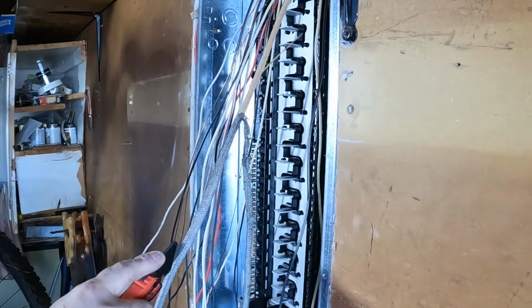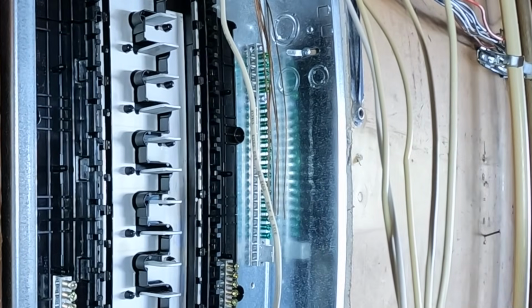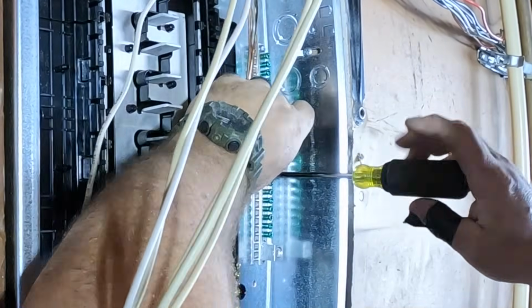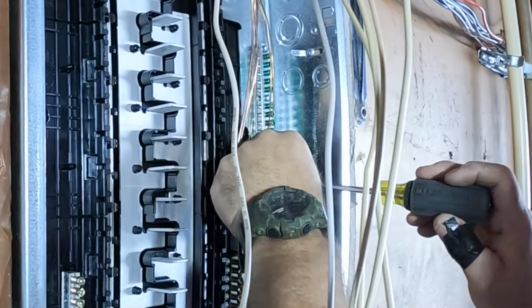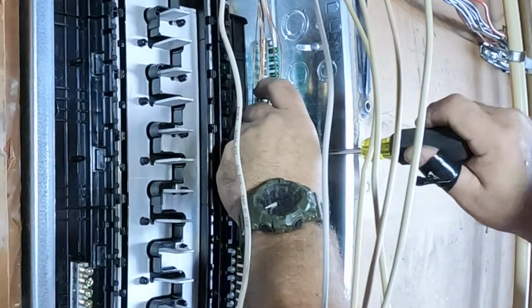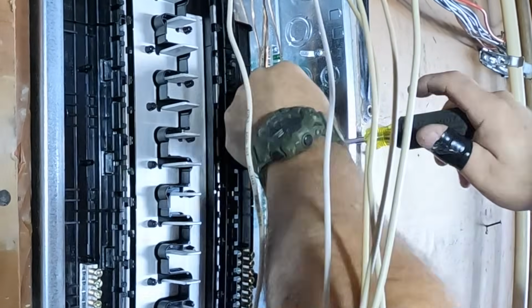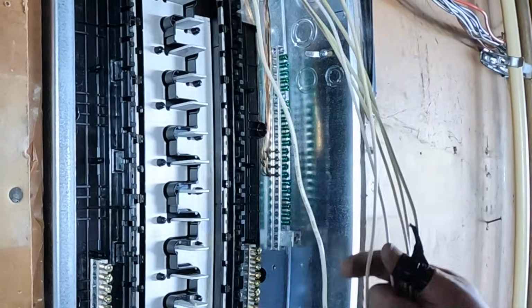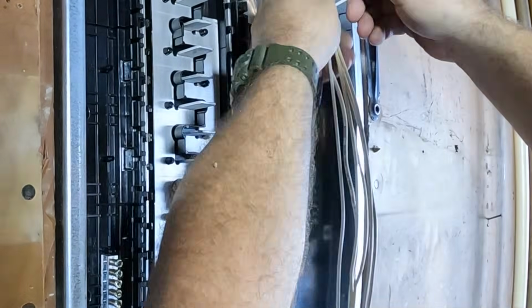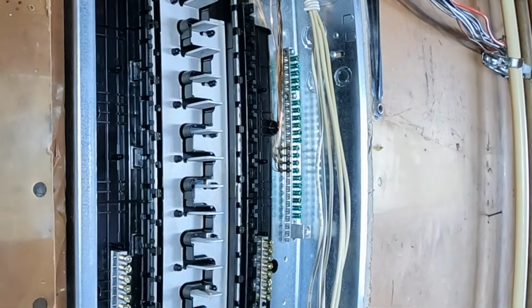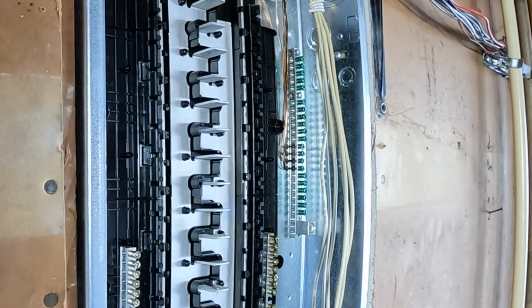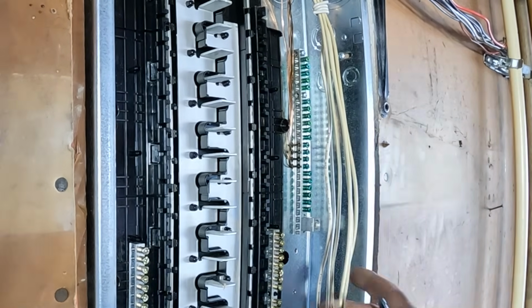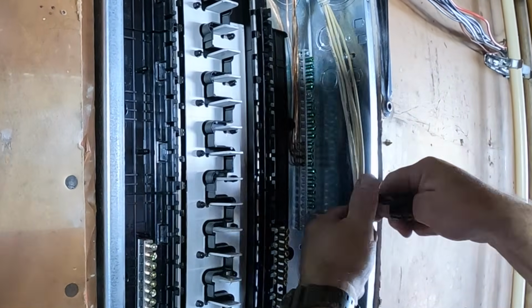Now, this is not the main disconnect. The main disconnect is outside. So this breaker inside this enclosure is only to turn off power to the panel. On the right there, you'll see all the green terminals. That's my equipment grounding conductor bar. So all of my equipment grounding conductors get attached to this bar, and this bar is bonded to the enclosure, so the whole enclosure now becomes bonded as well.